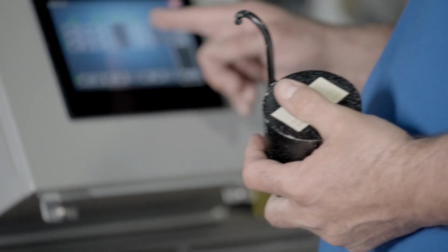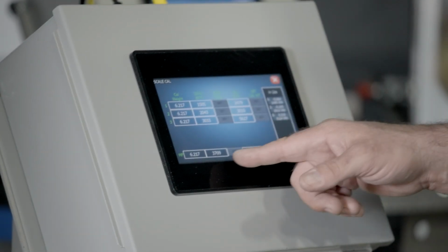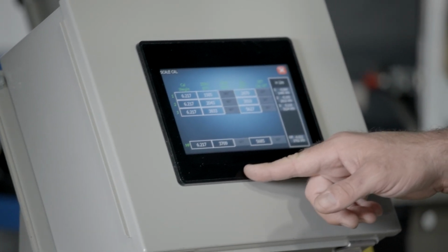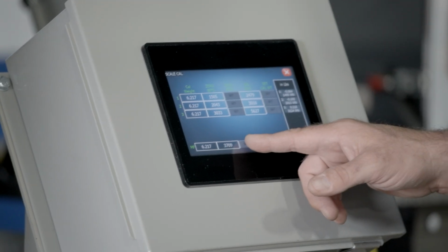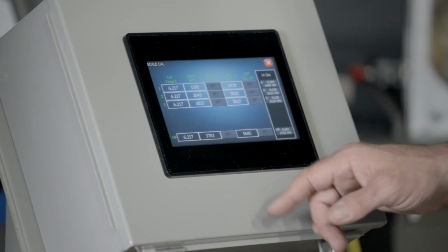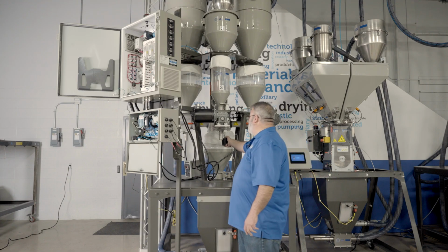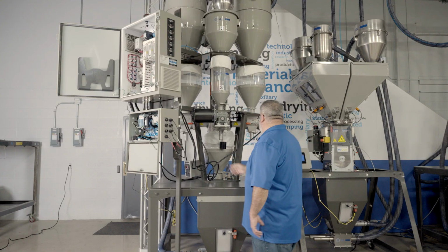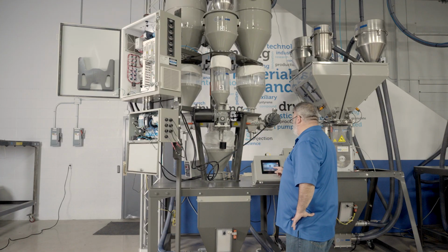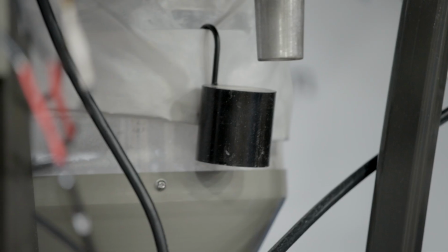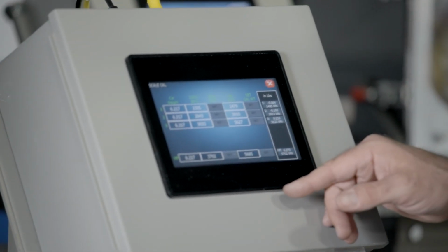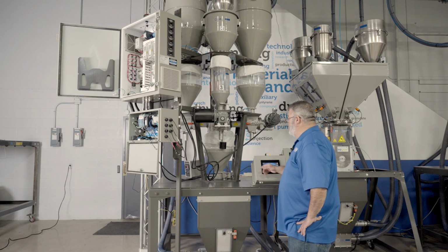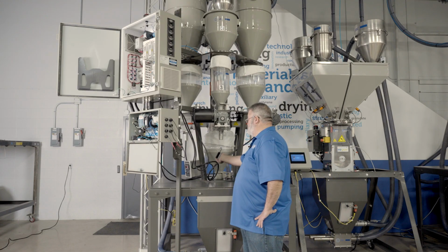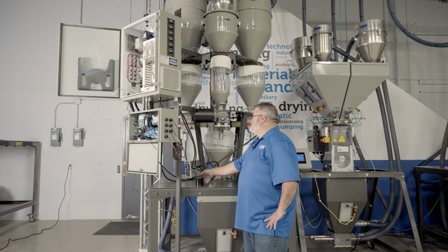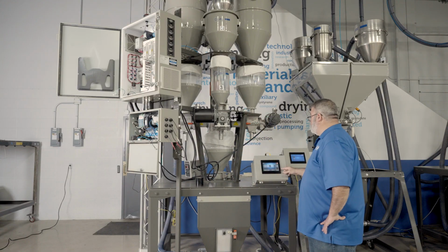It does. So the first thing we're going to do is the mass flow, since it's easier to reach. We'll hit set for the zero because we know it's empty. And then we'll hang your weight from the hopper. Once you get it hung up there, make sure your bit value isn't moving right here. Once it's done moving, hit set, and the mass flow is calibrated. You can repeat that process for the other 3 hoppers.